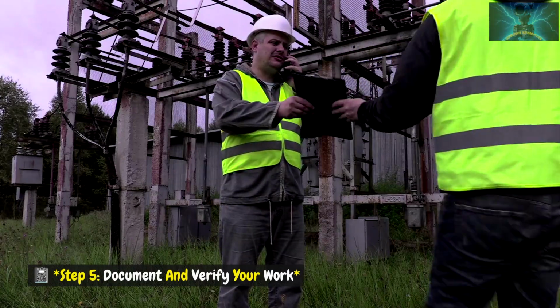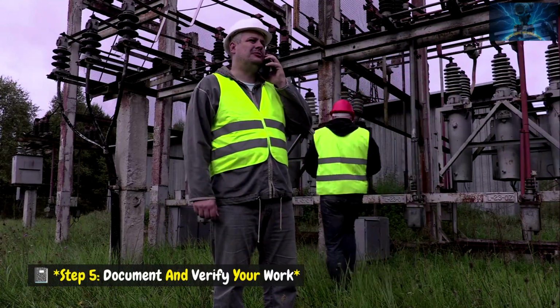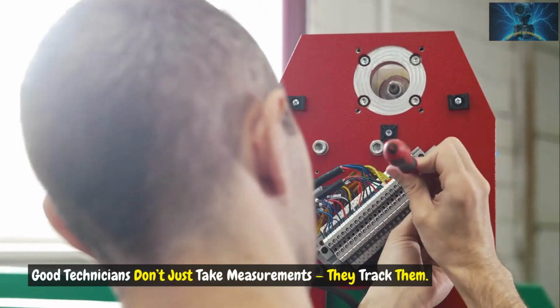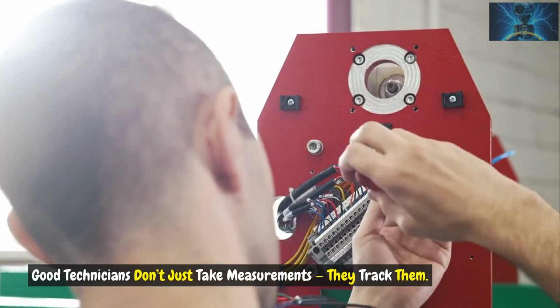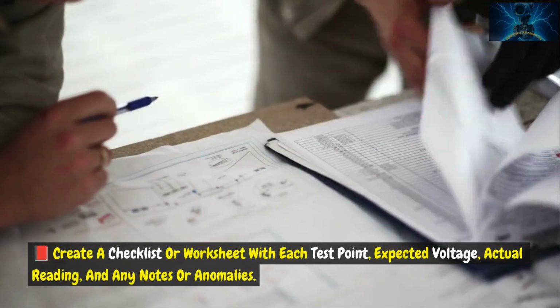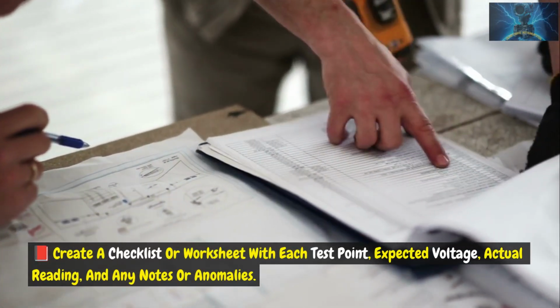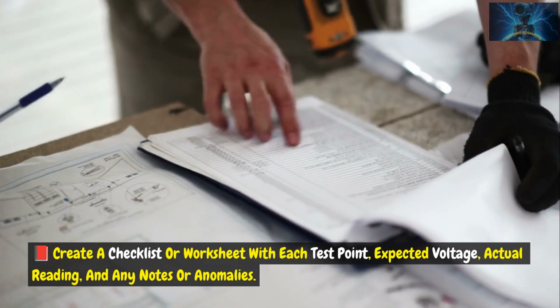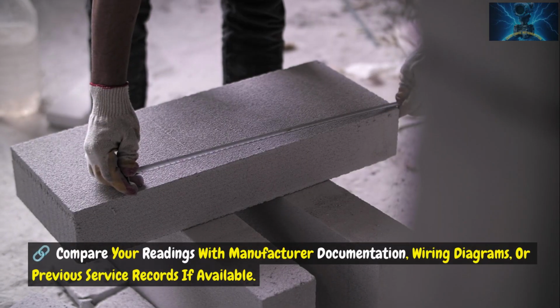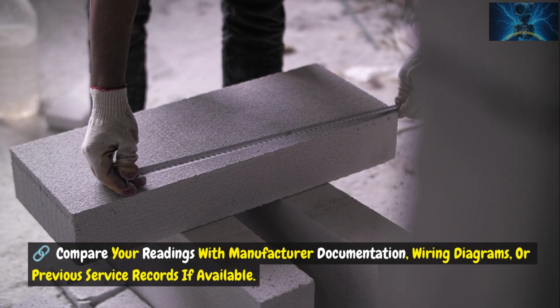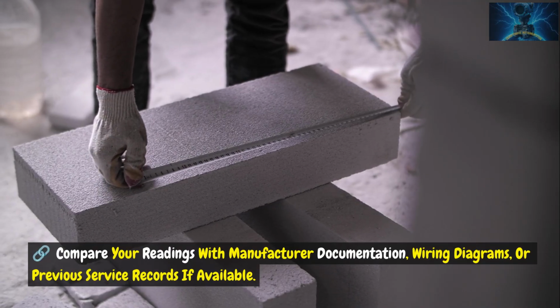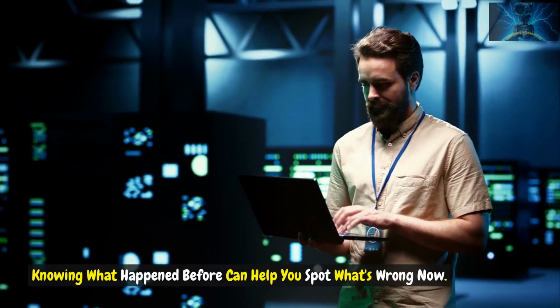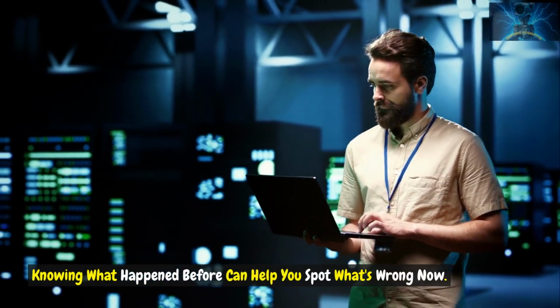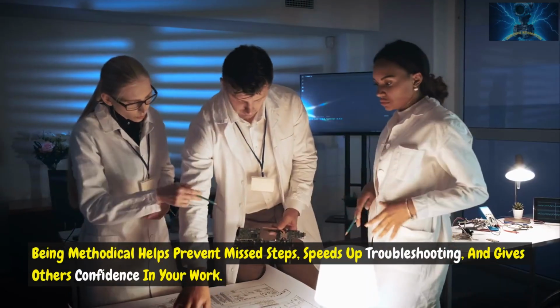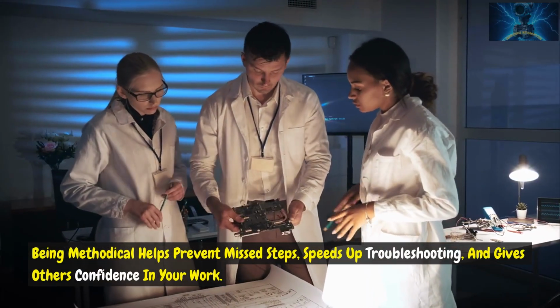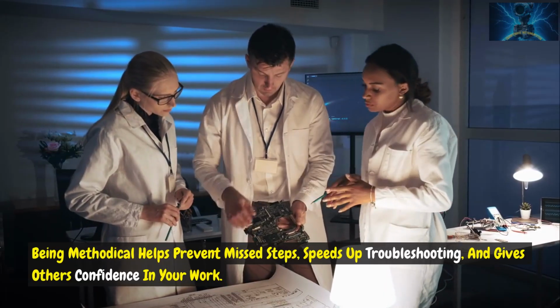Step 5. Document and verify your work. Good technicians don't just take measurements, they track them. Create a checklist or worksheet with each test point, expected voltage, actual reading, and any notes or anomalies. Compare your readings with manufacturer documentation, wiring diagrams, or previous service records if available. Knowing what happened before can help you spot what's wrong now. Being methodical helps prevent missed steps, speeds up troubleshooting, and gives others confidence in your work.